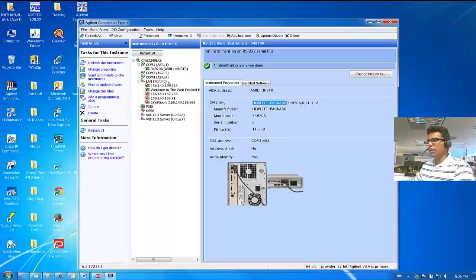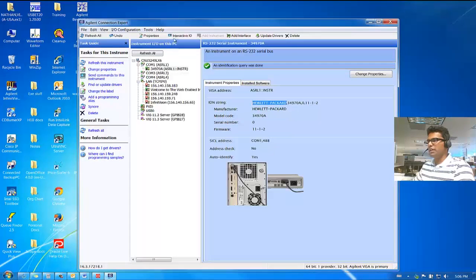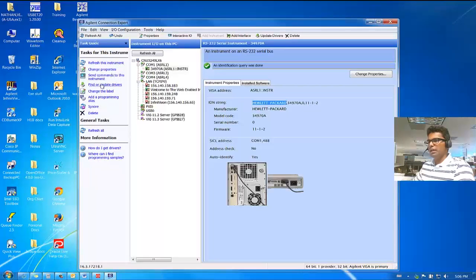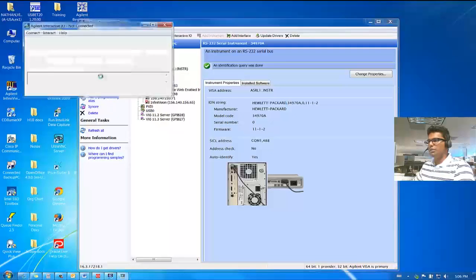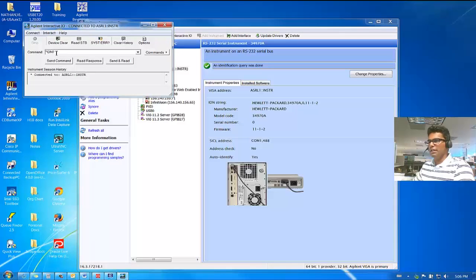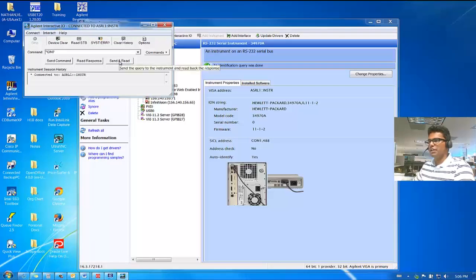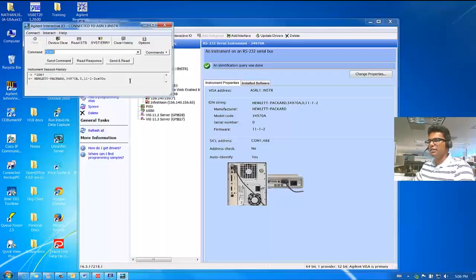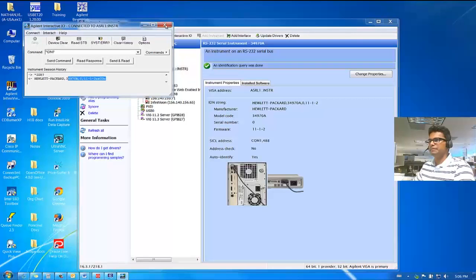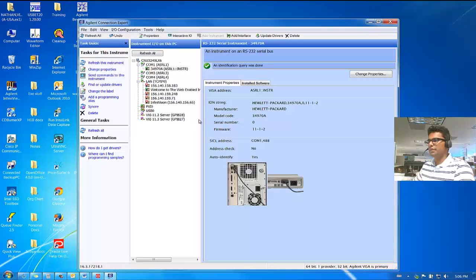Now, you can do a quick test with this instrument by clicking on Send Commands to this instrument. And you can do the Identify Query. Click on Send and Read. And you would see the same string as you saw here.